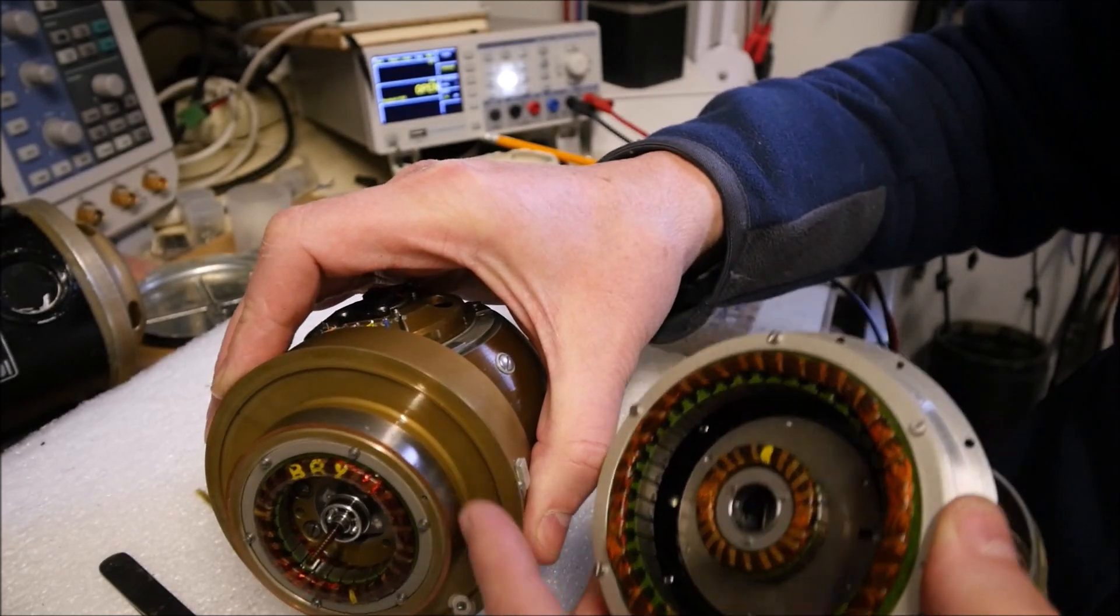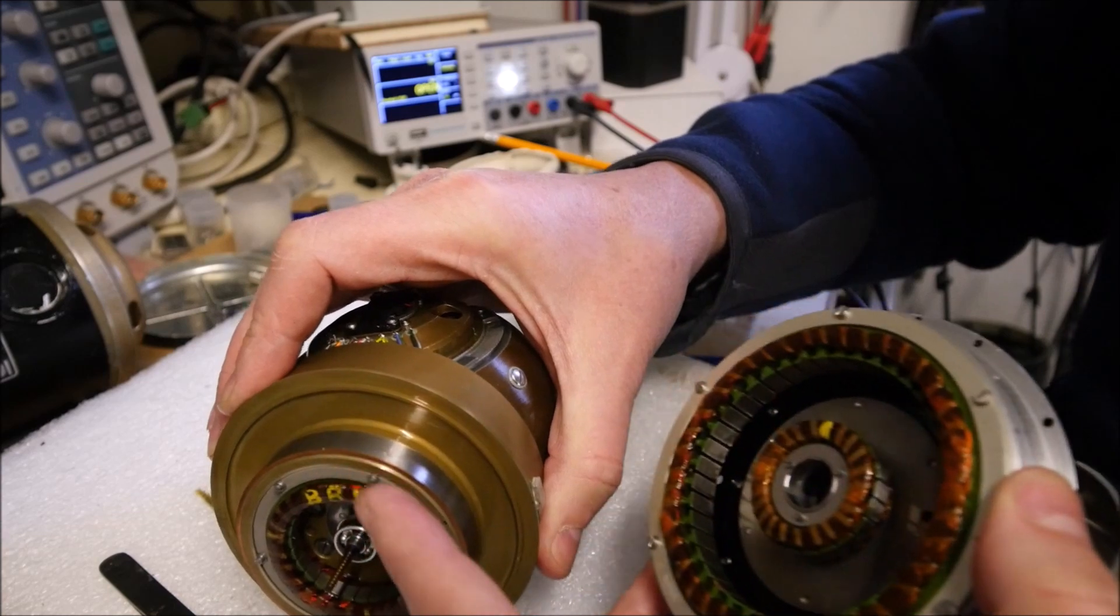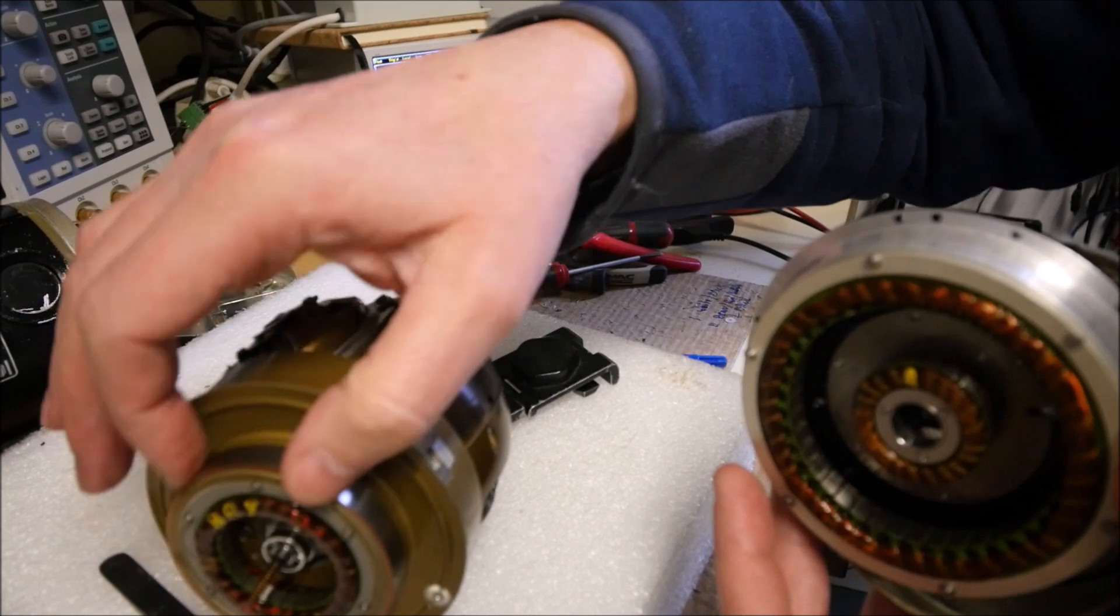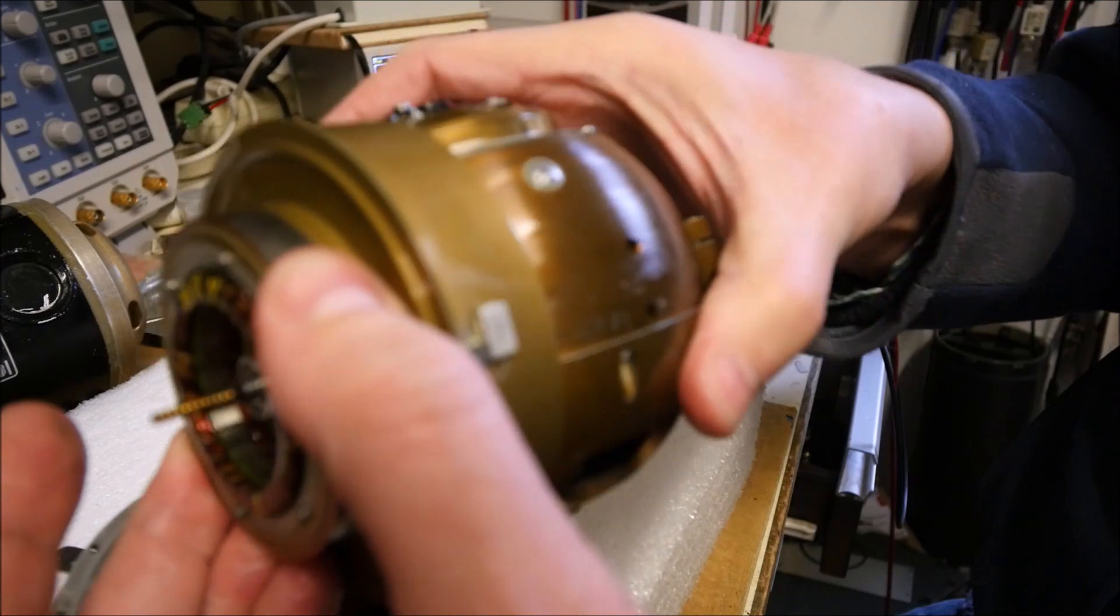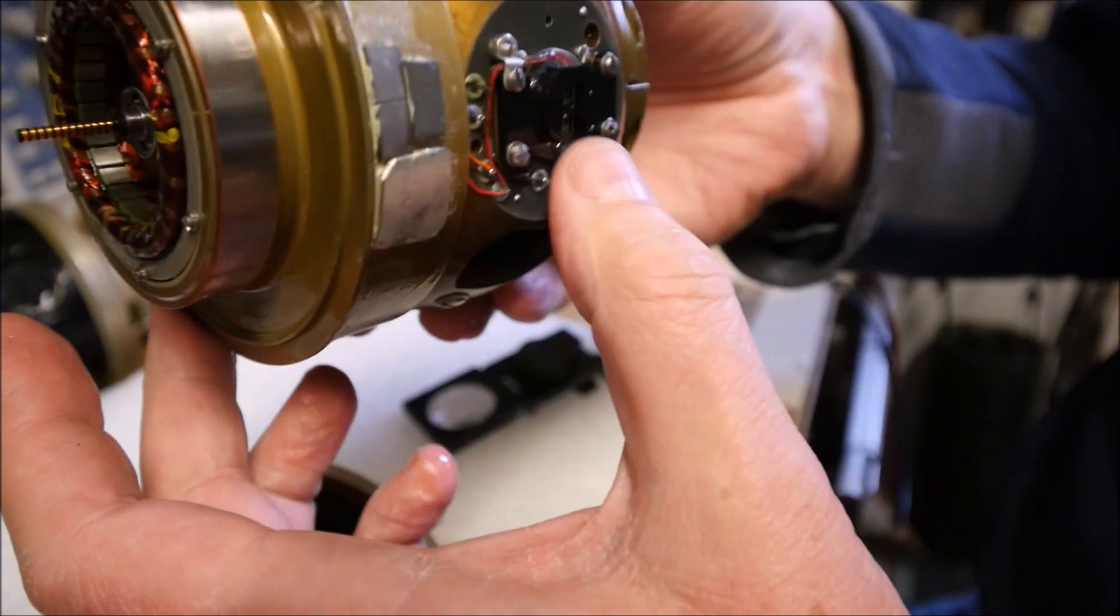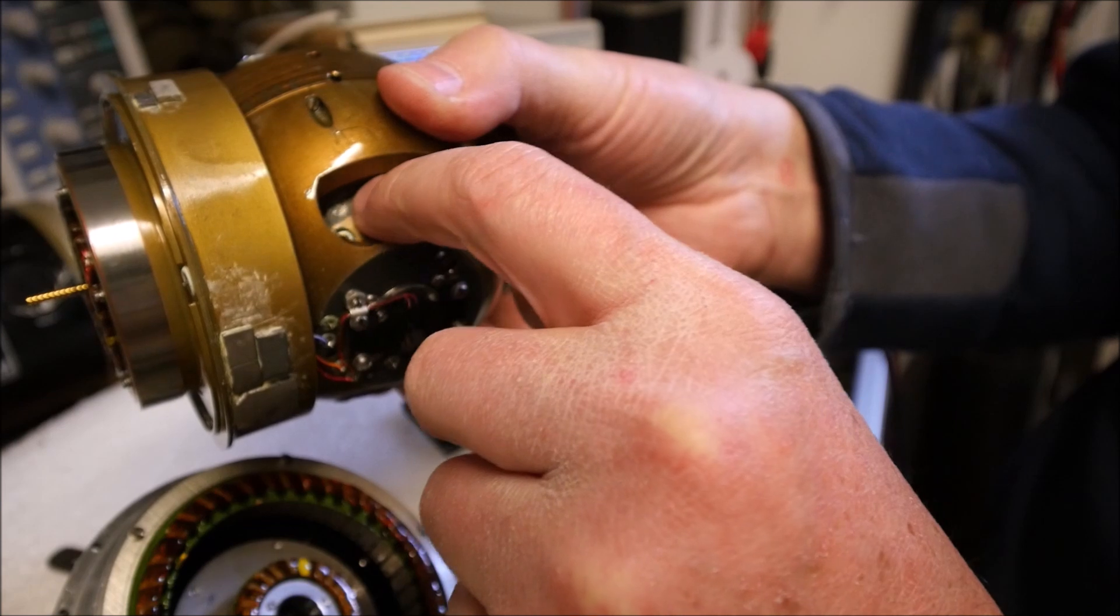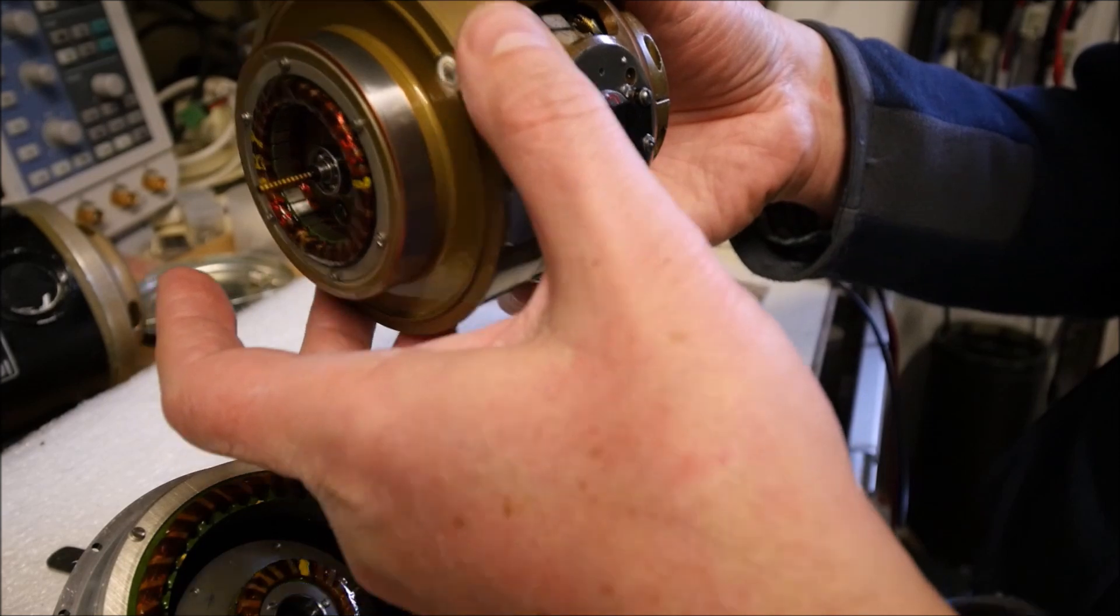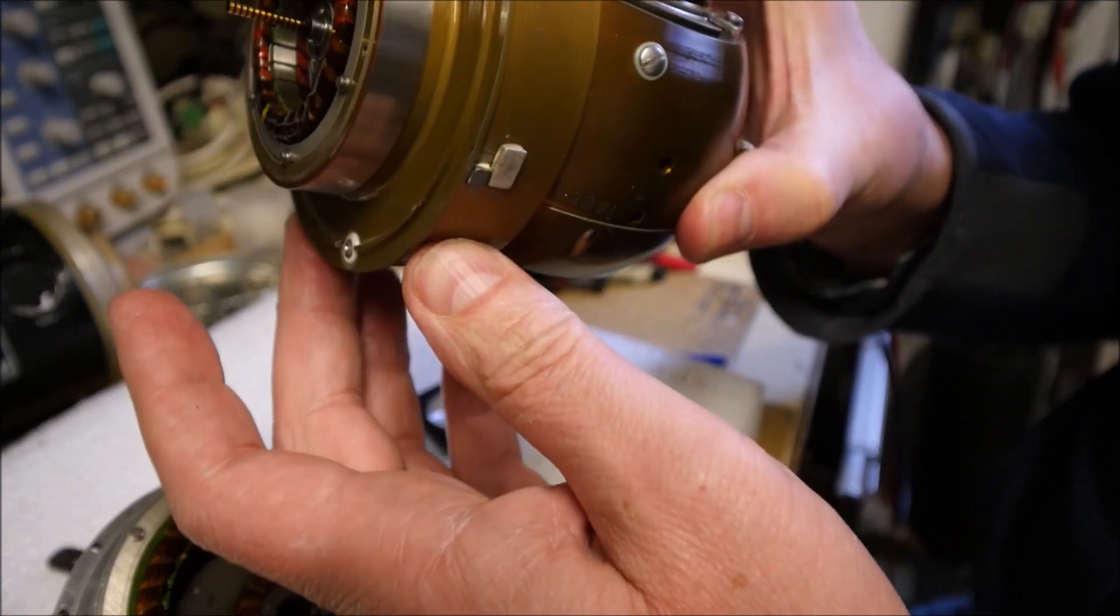So this is the rotor of the torque motor. So this is actually a short circuit. The torque is generated using eddy current on this rotor here. So the torque is applied on that axis here. So this permits to change actually the position of the internal gimbal here. And we should have another one inside for the second axis.